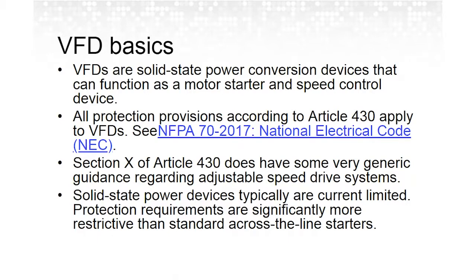Again, a VFD is a solid-state power device, and the device is current limited by the electronics within it. So the protection requirements associated with a VFD are typically much more restrictive than across-the-line starters. Sizing your overcurrent protection for a VFD at 200% of the full load current of a motor might be fine in certain applications for across-the-line starting, where you have overload protection included in a motor starter. But when you're trying to protect a VFD, especially against inrush currents associated with transients, that typically isn't acceptable.